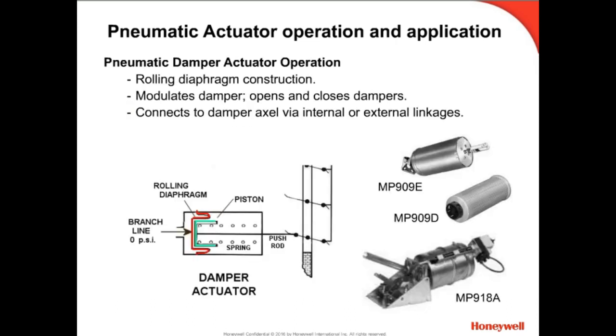Let's first examine pneumatic damper actuators. Damper actuators extend a push rod as increasing control signal air pressure inflates a rolling diaphragm chamber. The rolling diaphragm minimizes friction and wear, providing a very long and trouble-free actuator life. As the rod is extended, a return spring is compressed. As air pressure is decreased, the return spring retracts the push rod.